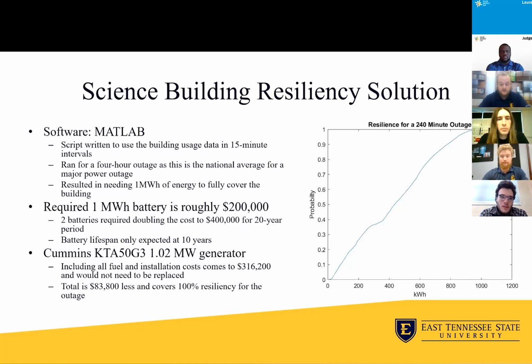From this, we researched alternative solutions, and the team settled on the Cummins KTA 50G3 1.02 megawatt diesel backup generator, as it came in at a total cost of $316,200, being $83,800 less than the two batteries. This price includes the generator, all necessary hardware, and ample fuel to cover the 4-hour outage.